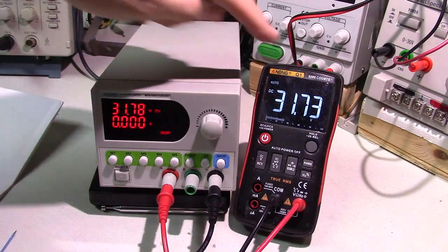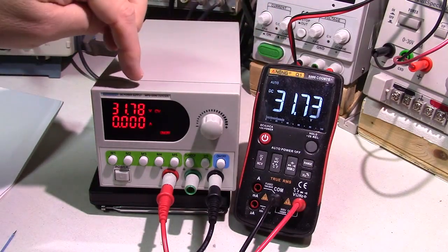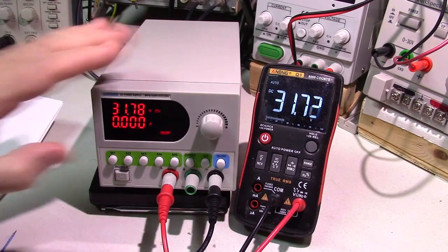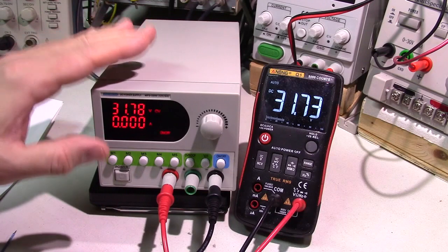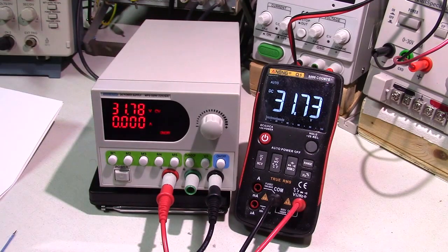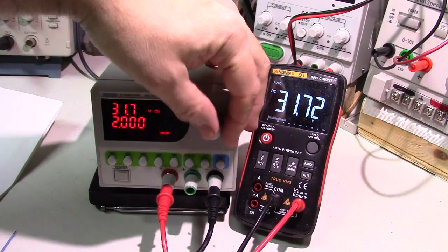Now it shows 31.78, 31.73 volts. I believe that the meter is more accurate even than that, so this is the reference standard because Matrix Technology accurately calibrates this before they ship it. To change the voltage, you hit the voltage button right there.